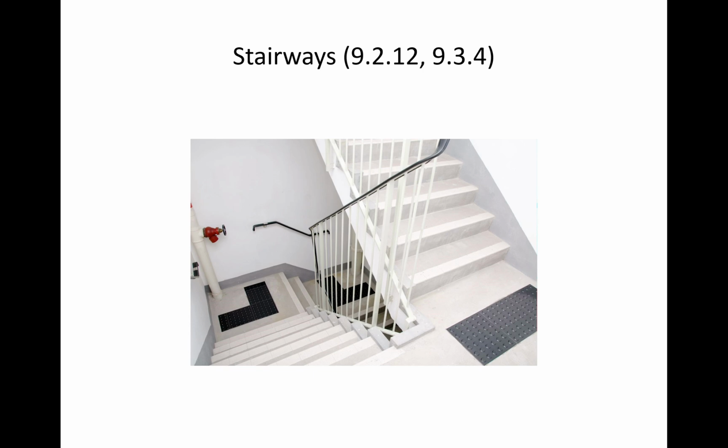The second case, and the more common case, is when the stairway is of non-combustible construction, the stairway itself and its enclosure. In this case, the sprinkler shall be provided in two locations, at the top and at the bottom, below the lowest landing, unless the space below the lowest landing is blocked off. In this case, a sprinkler shall be provided only at the top.